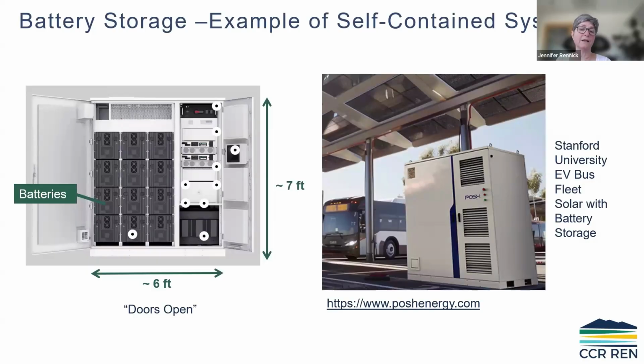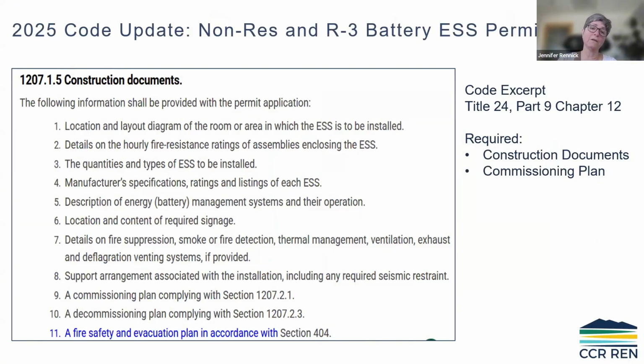So we're finding that it's good to understand the size of some of these commercial batteries, but you're going to need some extra consulting help is where I'm going with this. And part of the 2025 code update too, again, you're going to find this in Title 24, Part 6, Chapter 11, but there are construction documents that are required for the battery system. And this is why I'm saying we're not going to go through the formula today, because you're going to end up needing a battery consultant to do this, because you're going to need to have all of this on your construction documents. And what they added now for the 2025 code is a fire safety and evacuation plan that's required.